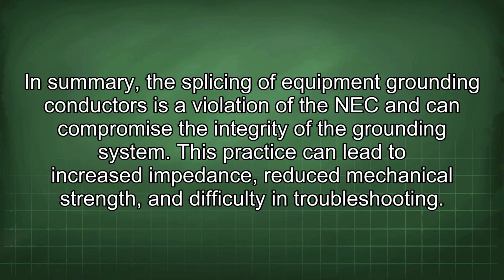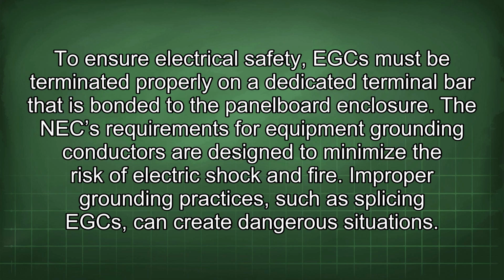In summary, the splicing of equipment grounding conductors is a violation of the NEC and can compromise the integrity of the grounding system. This practice can lead to increased impedance, reduced mechanical strength, and difficulty in troubleshooting. To ensure electrical safety, EGC must be terminated properly on a dedicated terminal bar that is bonded to the panel board enclosure. The NEC requirements for equipment grounding conductors are designed to minimize the risk of electric shock and fire.